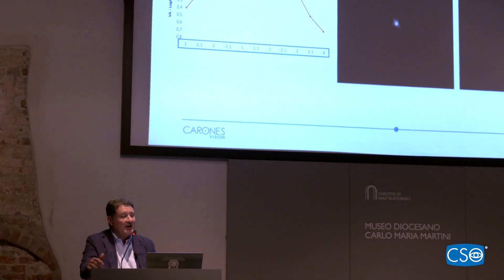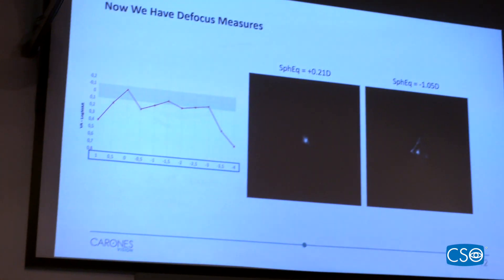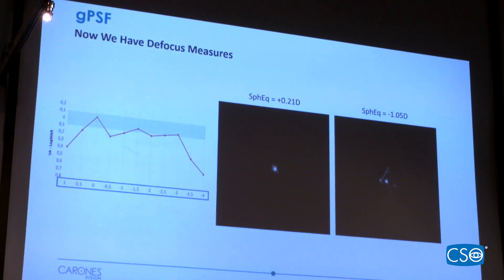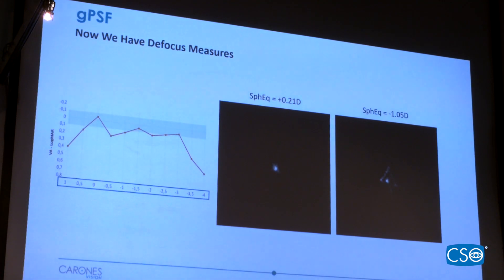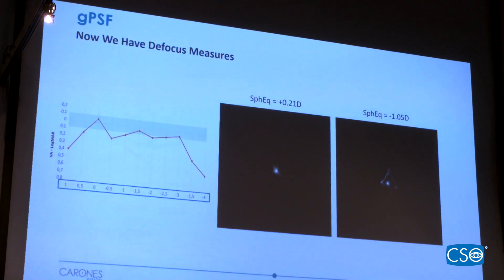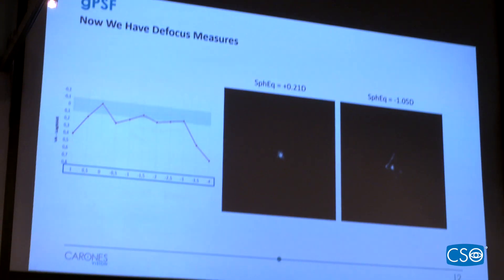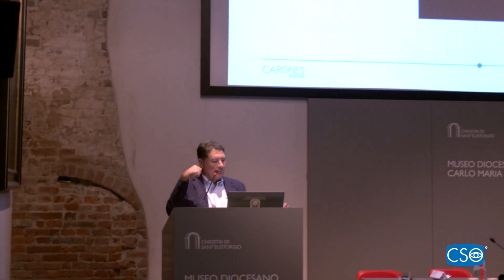Here is where we are now: we have a defocus measurement plotted on the x-axis, and we are now able to measure and plot the defocus — not based on lenses placed in front of patients' eyes, but derived objectively.